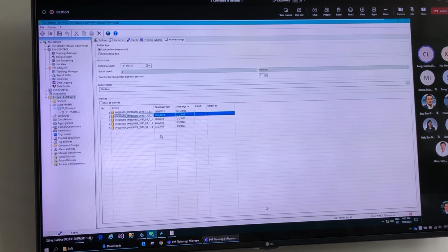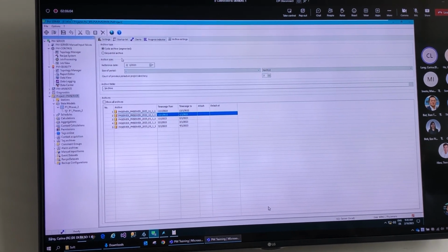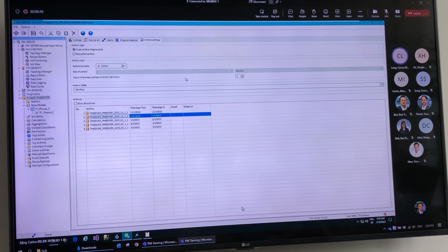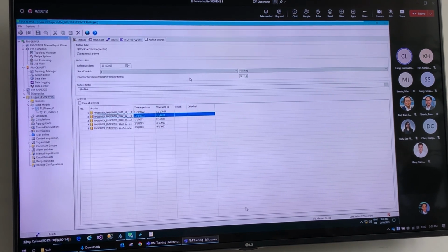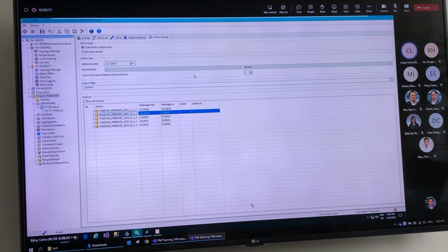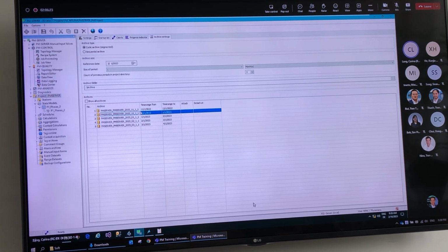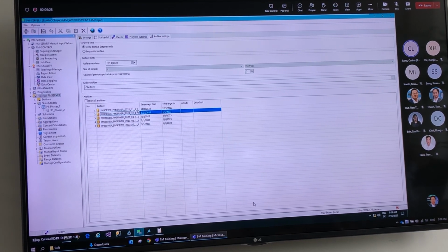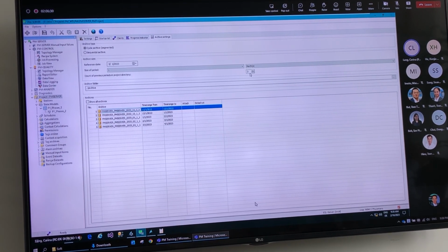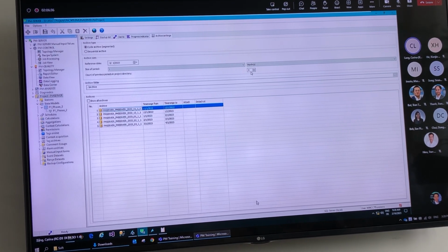And when we go to the next archive database, because we have defined a specific archive size, so which data we want to save within one archive before we create the next one, and we create the next archive automatically, as we are out of this range, then the oldest archive will be deleted, so that we have only, in this case, 3 older archives available in the project.